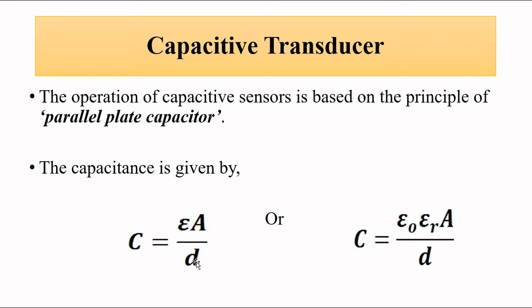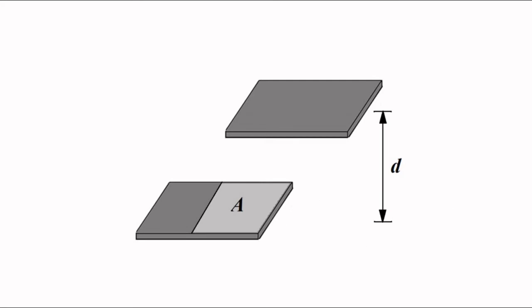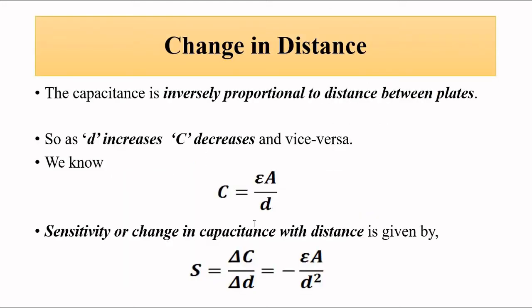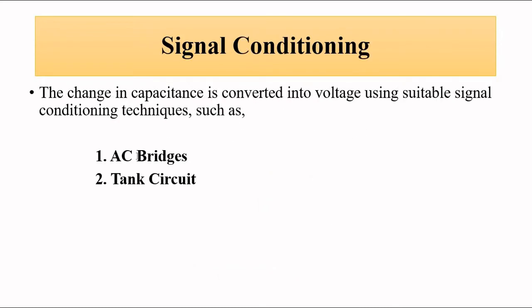The change in capacitance depends on the liquid level in the container. Capacitance is inversely proportional to distance between the plates — as d increases, capacitance decreases and vice versa. Capacitance is directly proportional to overlapping area. This change in capacitance can be converted into a suitable voltage or current signal using signal conditioning techniques such as AC bridges or a tank circuit.